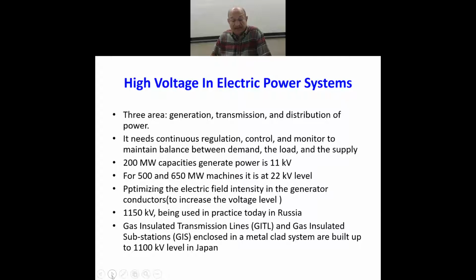We would like to increase the voltage, but there are constraints in the machine to go for higher voltage. You can imagine when it is 650 megawatt at 22 kV, the magnitude of the current would be very, very large. We'll calculate it.